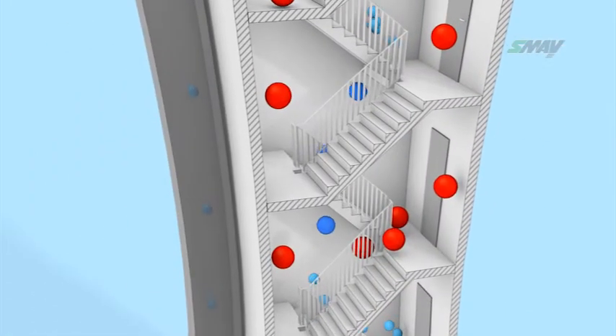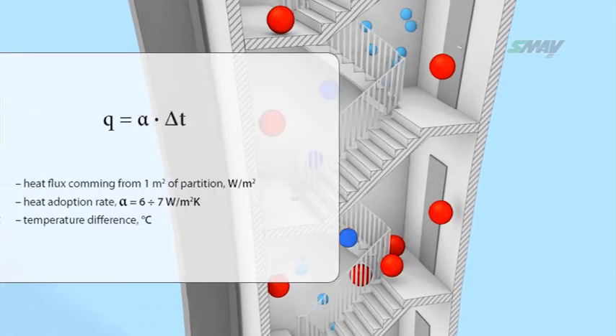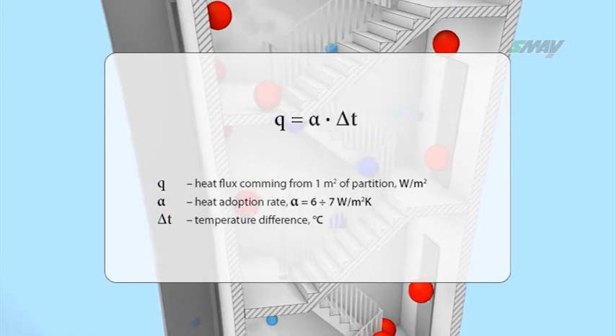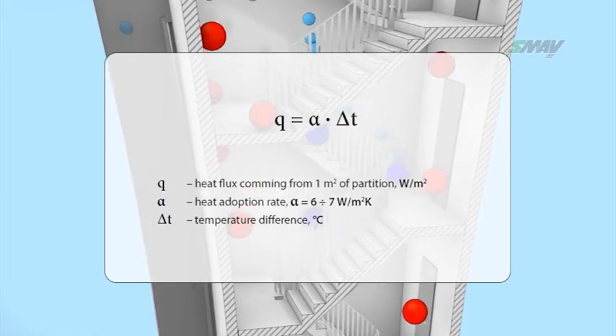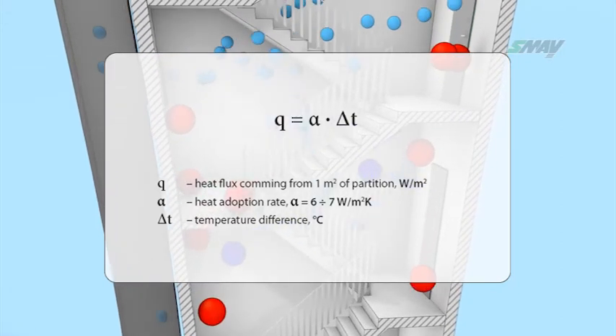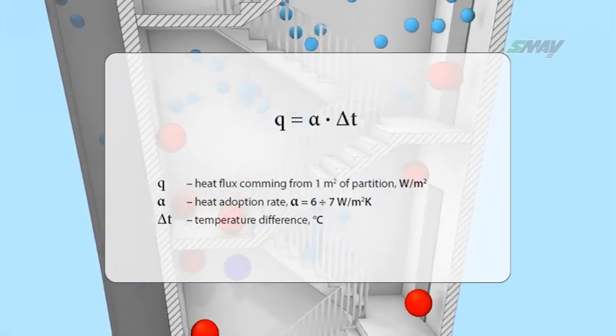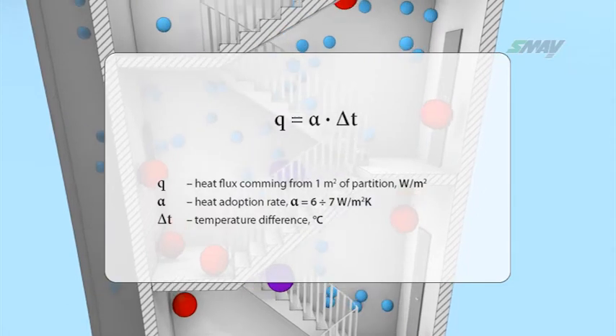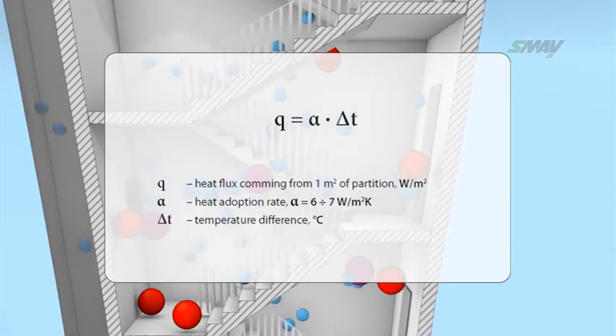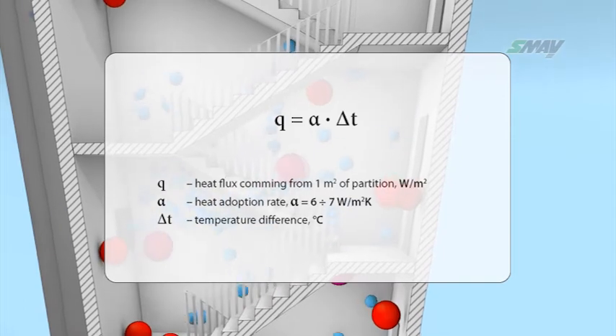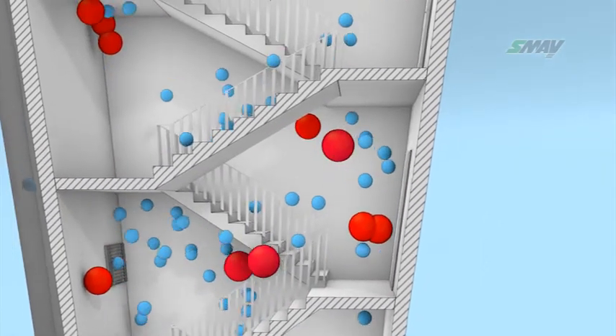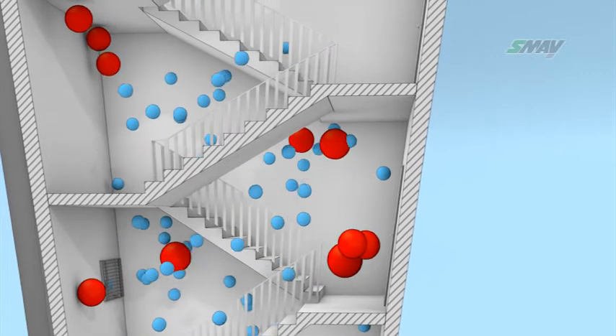The stack effect occurs due to the heating up of air particles by walls and stairs. The amount of heat dissipated by the walls is proportional to the difference in temperature between the air and the partitions. For example, if the temperature difference is 20 degrees, the walls may dissipate up to 140 watts from every square meter, as a result of which air density falls, causing buoyancy to push it upwards.